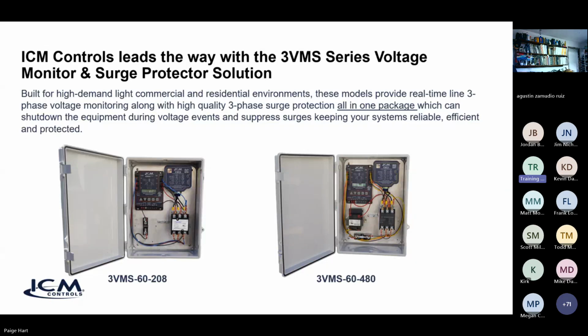So ICM came up with a solution and leads the way by offering you the 3VMS series voltage monitor and surge protector. What this does is combine the benefits of both voltage monitoring and surge suppression all in one package, and provides a means to break the service voltage for 60 amp services, 60 amp loads. Again, it's built for high demand and light commercial and residential environments. They provide real-time three-phase voltage monitoring along with very high quality three-phase surge protection all in one package. And you can shut down the equipment by breaking that main service voltage in the event that you have a problem with your three-phase voltage, which is a big deal. This keeps your equipment running reliably, efficiently, and protected.